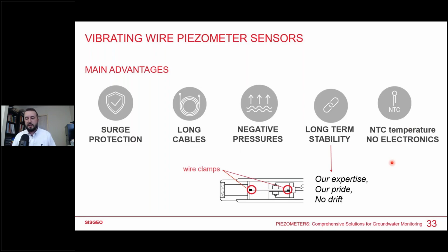Important to note that this kind of technology does not have many complex electronics. Complex electronics is, for example, a 4-20 milliampere transducer or converter that I spoke about before. Here you have no electronics, so no risk of failure due to electronics. So it's a very, very stable and long-term sensor. It's really appreciated in a structure where you have to measure for decades. Here, long-term stability is a very important parameter, also linked to the expertise of the manufacturing.